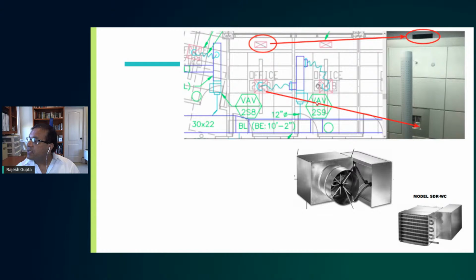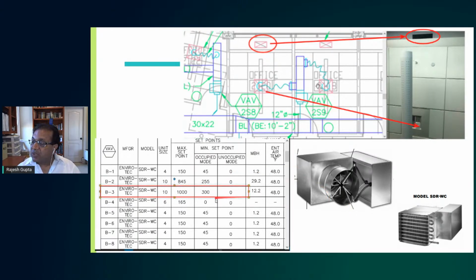So this is one VAV, and this is the feed supply, and this is the return air. This is how the VAV valve looks. This damper here is controlled by these gears, which are plastic gears like you see in an RC plane, so over time they basically break down. Now, if you look at the spec sheets, this is a different room, but you can see nominal is 45 CFM, maximum 150 for this particular room.